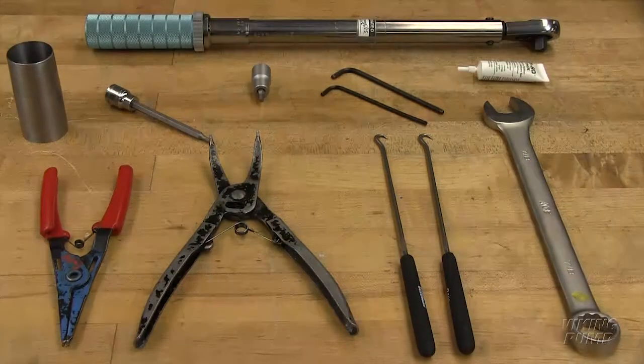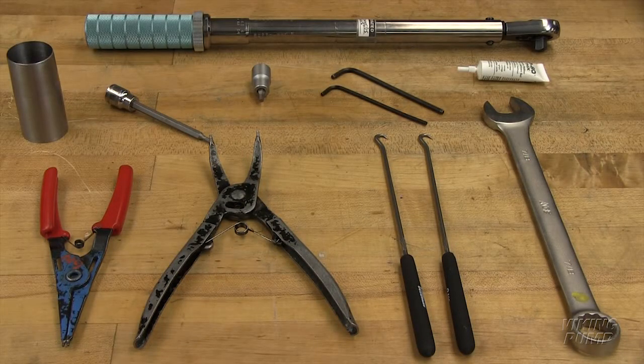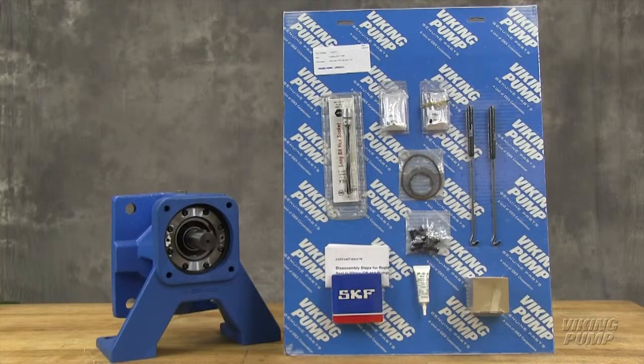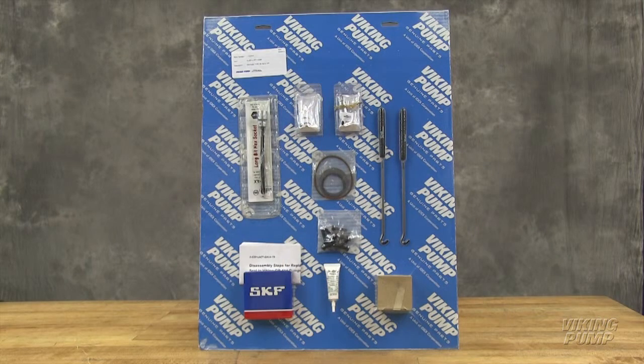A complete listing of tools and part numbers can be found in the service manual. For newer pumps, seal kit part numbers can be found on a hang tag on the pump. For older pumps, or if the tag has been removed, contact your local authorized Viking pump distributor with the model and serial number of the pump to obtain these part kit numbers. The pumps covered in this video are GP-414 series pumps with Type 8B mechanical seals. The seal kit includes a ball bearing, mechanical seal, O-ring, retaining ring, seal washer, drive key, shims, and associated hardware.